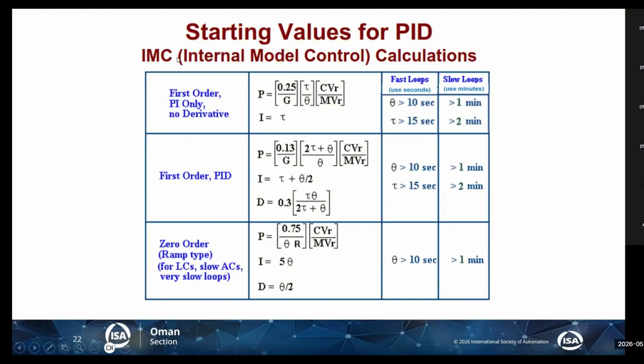So this is also a good tuning method called IMC, internal model control. This is basically for first order transfer functions and zero order. I haven't myself tried this on second or third order, only on first and zero. So how do we calculate the proportional gain? Using this equation: 0.25, which is a constant number, divided by process gain. We have to identify the process gain from the trend, either historian data, or if the operator allows me to do a step test, I will step the controller, see the effect and calculate the process gain.